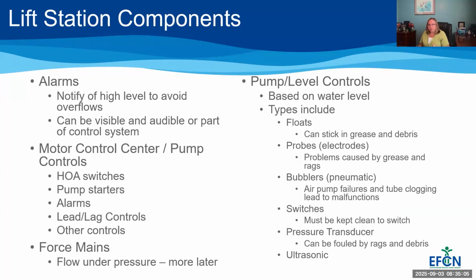And then your motor control center or your pump controls, these are your HOA switches, and your HOA is not your homeowner association. And if you don't know what HOA is, you need to get familiar with it for the test, but it's hand-off auto, right? So you can tell your pump essentially how you want it to run. You want it to run with you controlling it by hand? Is it off, or do you want it to run automatically based on your level controllers?